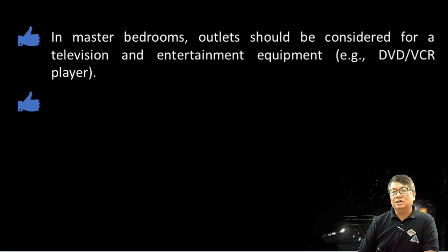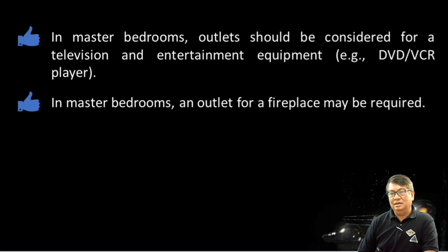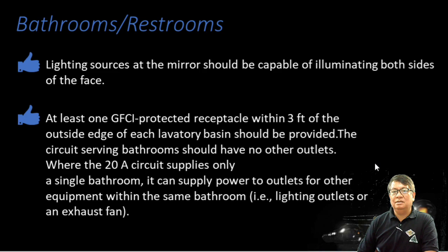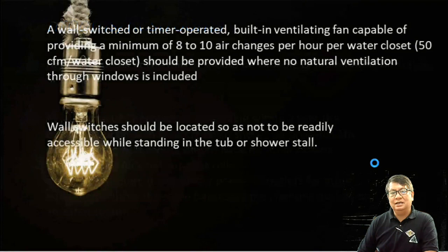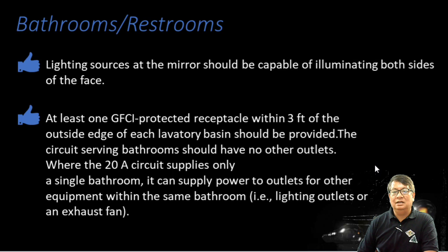Baka manonood ng DVD and other audiovisual equipment. So, lagyan natin ng outlet yan. Master's bedroom's an outlet for a fireplace may be required. Okay. So, lighting sources at the mirror should be capable of illuminating both sides of the face. Oh, importante yan. Mayroon din tayong kailangan na GFCI protected receptacle within 3 feet of the outside edge of its lavatory basin sa mga bathrooms, no? Diyan sa mga bathrooms, sa mga private bathrooms sa mga master's bedroom.